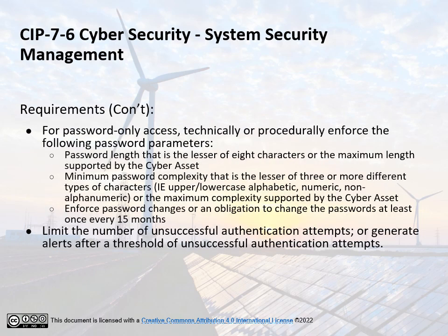CIP-007-6 System Security Management. Requirements continued. For password-only access, technically or procedurally enforce the following password parameters: password length that is the lesser of 8 characters or the maximum length supported by the cyber asset. Minimum password complexity that is the lesser of 3 or more different types of characters, i.e., upper case, lower case, alphabetic, numeric, non-alphanumeric, or the maximum complexity supported by the cyber asset. Enforce password changes or an obligation to change the passwords at least once every 15 months. Limit the number of unsuccessful authentication attempts, or generate alerts after a threshold of unsuccessful authentication attempts.